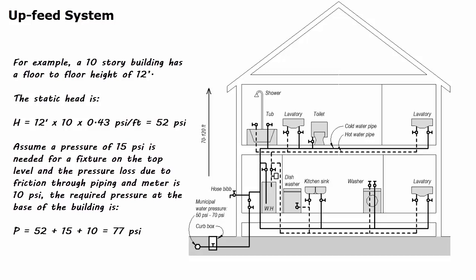Assuming a pressure of 15 psi is needed for a fixture on the top level and the pressure lost due to friction through piping and meter is 10 psi, the required pressure at the base of the building is 52 plus 15 plus 10, which equals 77 psi.